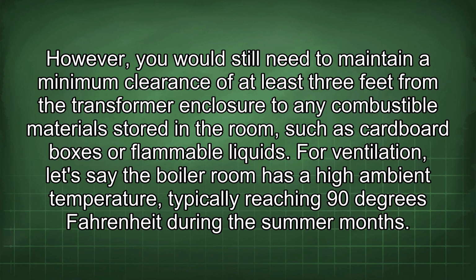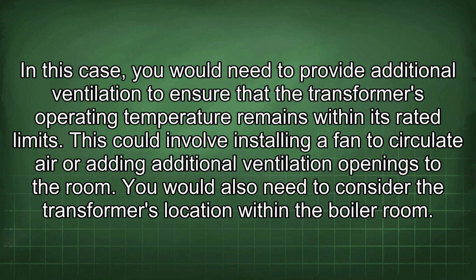For ventilation, let's say the boiler room has a high ambient temperature, typically reaching 90 degrees Fahrenheit during the summer months. In this case, you would need to provide additional ventilation to ensure that the transformer's operating temperature remains within its rated limits. This could involve installing a fan to circulate air or adding additional ventilation openings to the room.